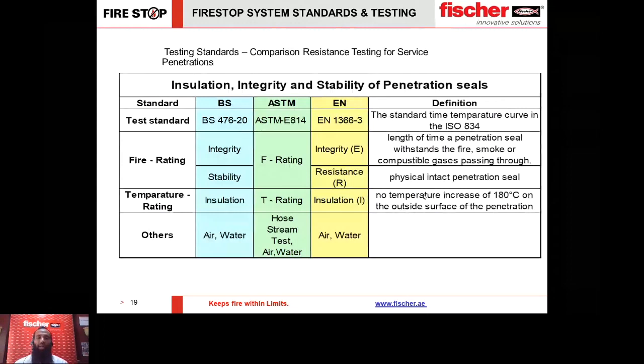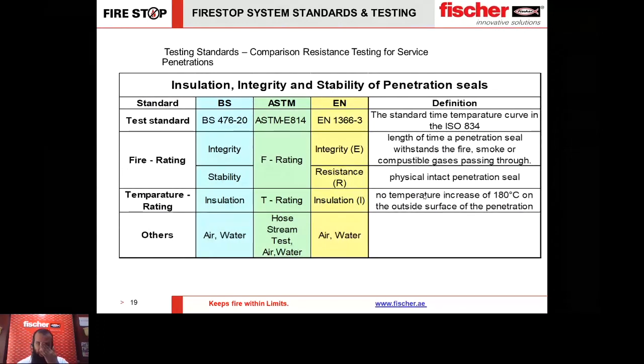These tests are done in a controlled environment. On a project site, somebody may break a fire barrier and make an opening of say 150 mm to pass a 25 mm conduit — the question is why such a large opening? It is very important to plan, especially the fire barrier layout, from the beginning of the project. If you plan the fire barrier layout and plan the openings within the fire barrier, you can save a lot of money — and fire stop material is really very expensive.